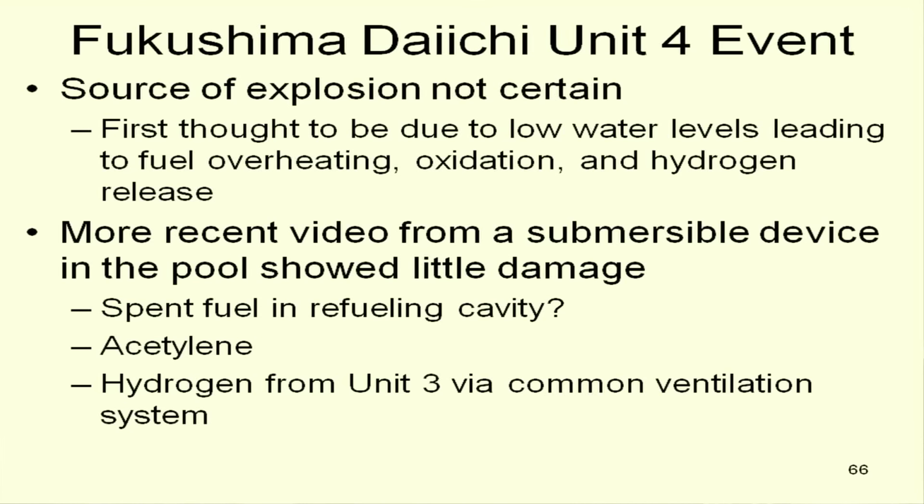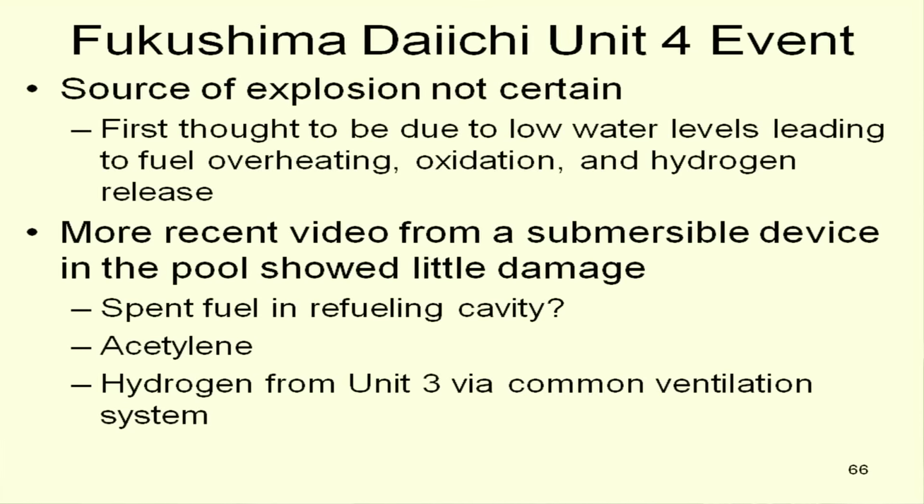And that persisted for some number of weeks, but then they did a couple of things. First, they got a submersible device, remotely controlled, and they sent it tooling around the fuel pool. I have a little 2-minute video someplace, and I saw that, and the first immediate reaction was, no, there's no melting here. You could see the top of the assemblies. It looked very good in the pool. The pool was fairly clear. You could see 30, 40, 50 feet. There was some debris on top of the fuel assemblies, but of course the building exploded above it, so junk dropped down.